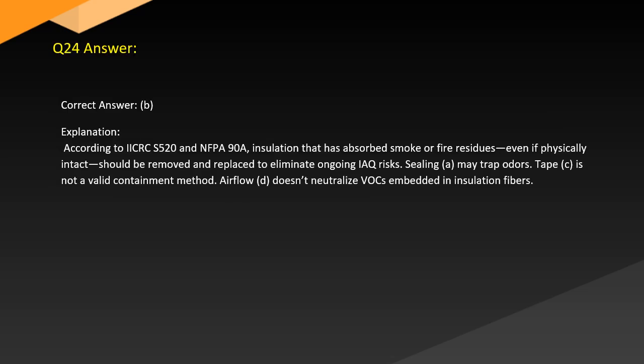Answer. Correct answer: B. Explanation: According to IICRC S520 and NFPA 90A insulation that has absorbed smoke or fire residues, even if physically intact, should be removed and replaced to eliminate ongoing IAQ risks. Sealing (A) may trap odors. Tape (C) is not a valid containment method. Airflow (D) doesn't neutralize VOCs embedded in insulation fibers.